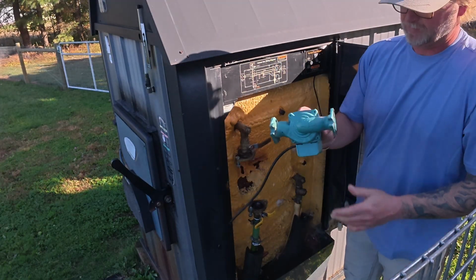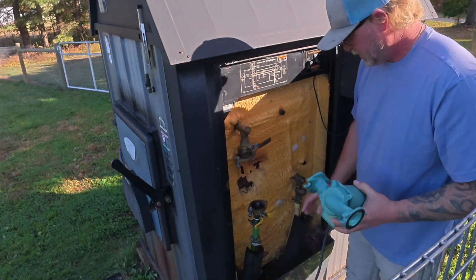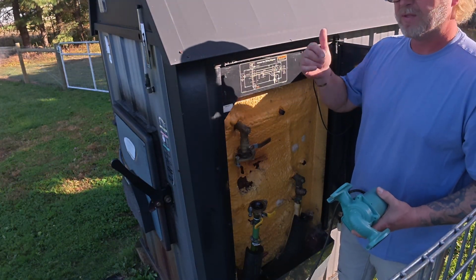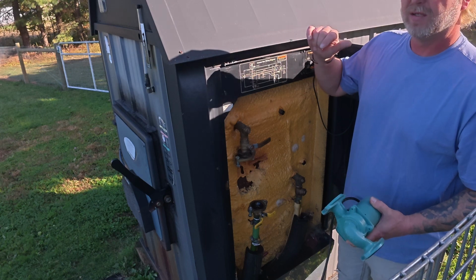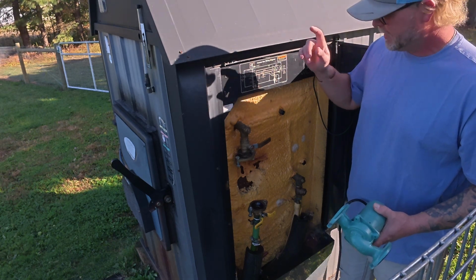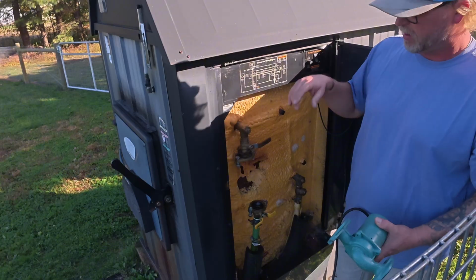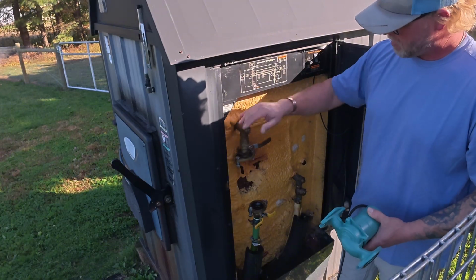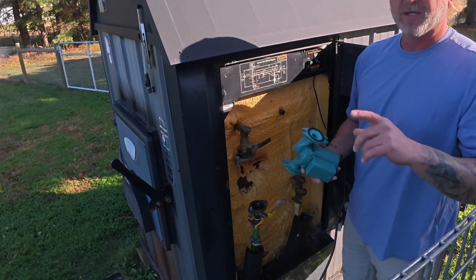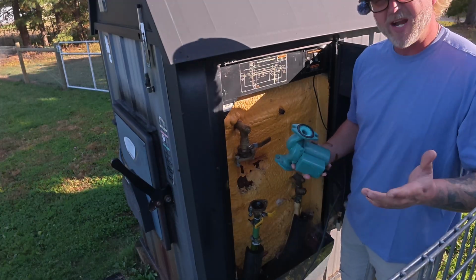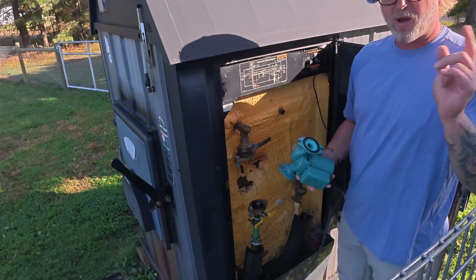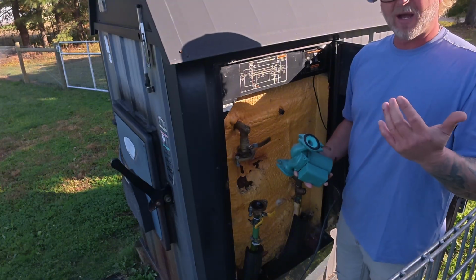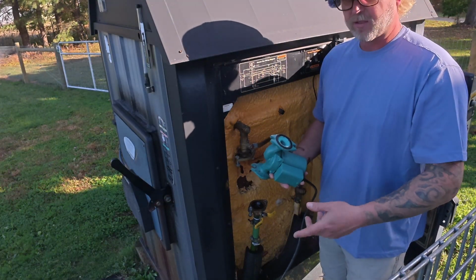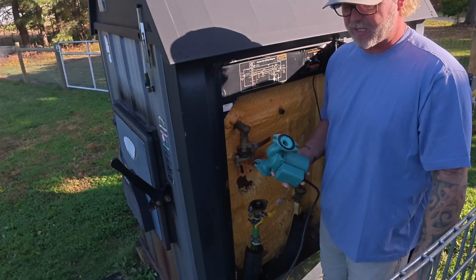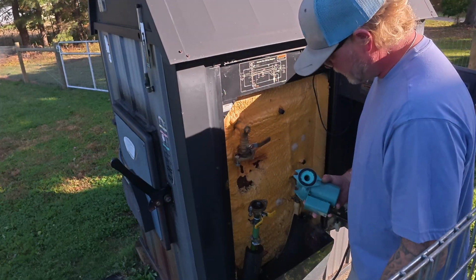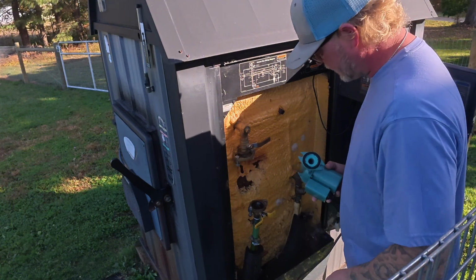So that's it, that's a circulating pump. What this does: the boiler heats up - there's about 325 gallons of water in a big jacket around the firebox. The firebox heats the water up, and the water comes out through the circulating pump and goes into the house. There's a heat exchanger in the top of the furnace, like a radiator in a car. All that hot water circulates through the heat exchanger, and when the house calls for heat, the blower kicks on, blows air across that hot heat exchanger, and that's the warm air that gets circulated through the house.